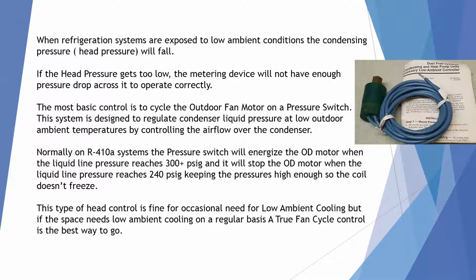When refrigeration systems are exposed to low ambient conditions, the condensing pressure or head pressure will fall. If the head pressure gets too low, the metering device will not have enough pressure drop across it to operate correctly. The most basic control is to cycle the outdoor fan motor on a pressure switch.